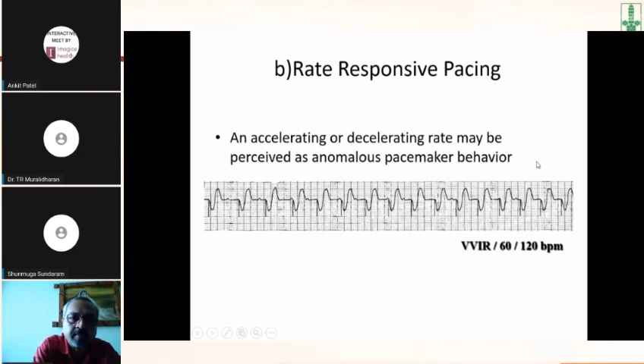The important thing is the hysteresis of the pacemaker. When all of us go to sleep at night, the intrinsic heart rate falls to as low as 40 beats per minute. So if we keep the lower rate of the pacemaker at 60 or 70 beats per minute, as shown in this example, the patient will be pacing all the time, even at night when it's not desirable. We don't need to have that pacing at night. So basically, in some of the pacemakers we can switch on hysteresis, which allows a lower rate between sensed events to occur. As shown to the left of the panel, the lower rate is 70 beats per minute, and we can set the hysteresis rate at 50 beats per minute, so that once we switch on the hysteresis function, the pacemaker will fire at night only when the heart rate falls below 50.